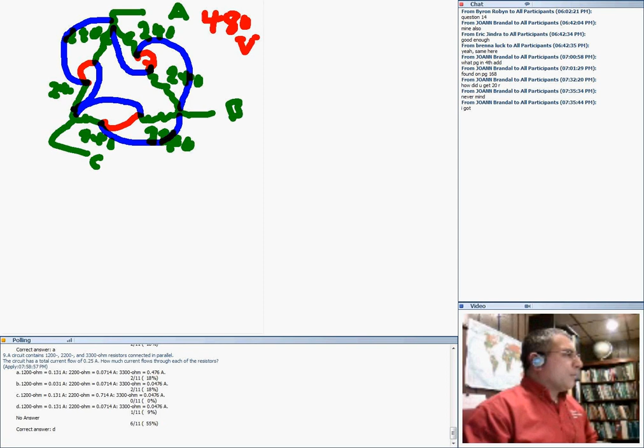What it means is you put coil 1 in phase and tie them together like this - that's what we've done. In every phase, you put the coils together, so this becomes 240, and this is 240. If you do it this way, the system will be a 240 3-phase system. So let's just say this is a 50 horsepower motor, 3-phase, commonly used - you can use it in an air handling unit and so forth. This horsepower motor, I can run at 480 or 240, no problem.